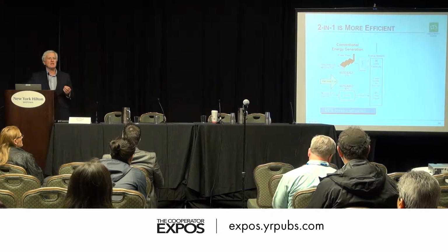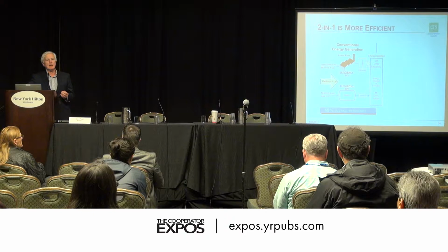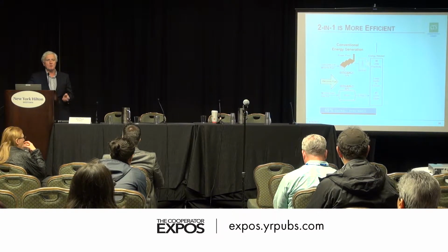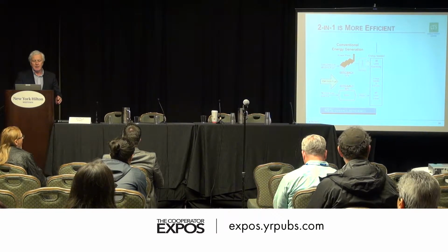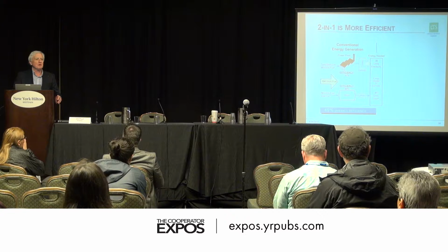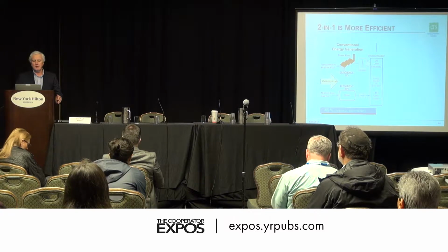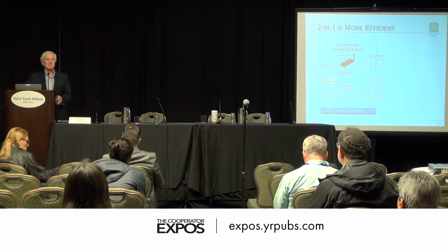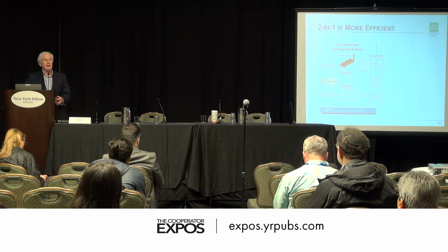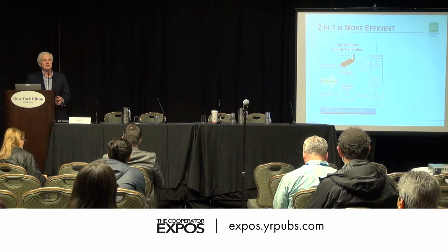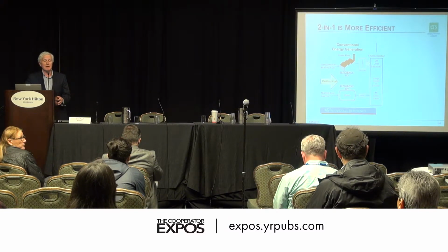If we need 30 units of electrical energy and 45 units of thermal energy, for example—somewhat arbitrary, but the units are the same measure—it's going to require more input fuel to get that energy. For the electrical, to get 30 units out, we'll have to put in 98 units of fuel, or thereabouts. And for the boiler at 80% efficiency, we'll need 56 units of energy in to give us the 45 units of heat we need in our building.